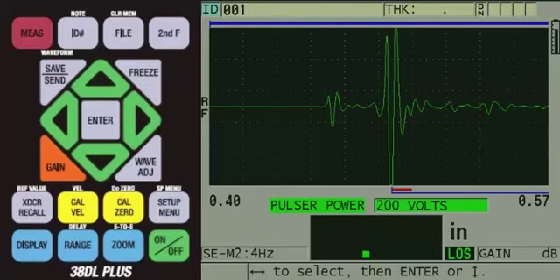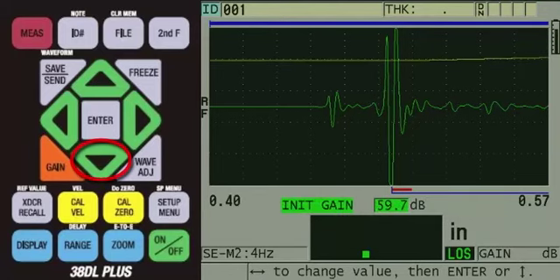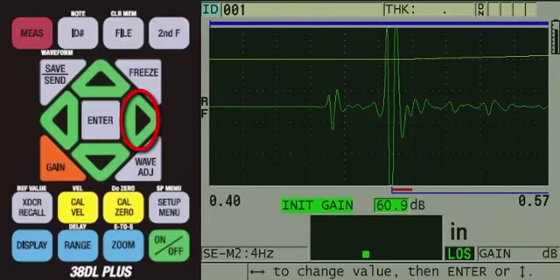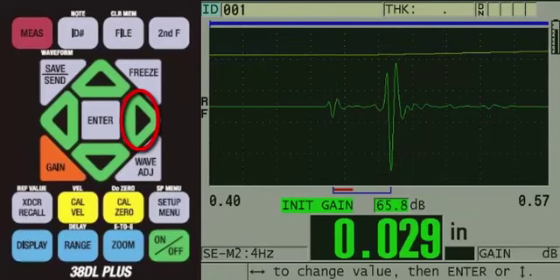The delay line echo is still not large enough to be detected, so we need to increase the initial gain. To do this, we will press the down arrow to INIT gain. Then we will use the right arrow to increase the initial gain until the gauge is making the Mode 2 measurement. You will notice that due to the automatic gain control, the delay echo is still low in amplitude. This is fine as long as the gauge is making proper detection, which it is.